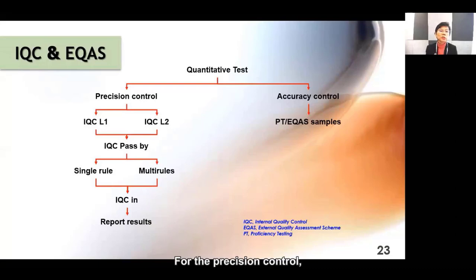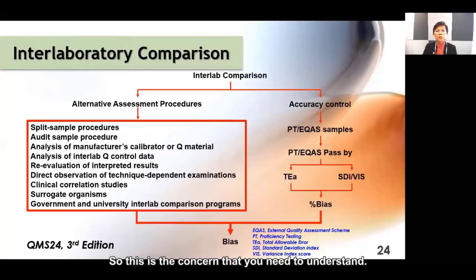For the precision control, usually you have internal quality control to help you do this. And usually you do 2 levels of control. It might be level 1 and level 2, or level 1 and level 3. So it depends on your choice. And here the QC has to be passed. It may be passed by a single rule or multi-rule, but it has to be passed before you report the result. So if your QC is out, you have to fix the problem and run the QC again, and when the QC is in, you can report the result. So you cannot report the result as long as your QC is out. So this is the concern that you need to understand.